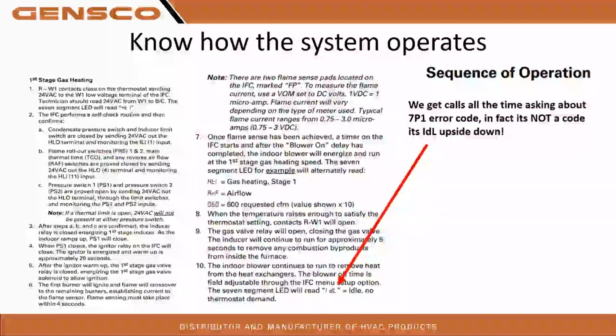In our install guide and service facts, we give you the sequence of operations. This one is out of an S-series furnace. It tells you for first stage gas heating what it's actually going to do step by step. That's very good for telling you, okay, we missed this step. Why? Do we have a switch out, or is the board simply making a bad decision? So we need to look at all these steps and see if it's actually working like it should.